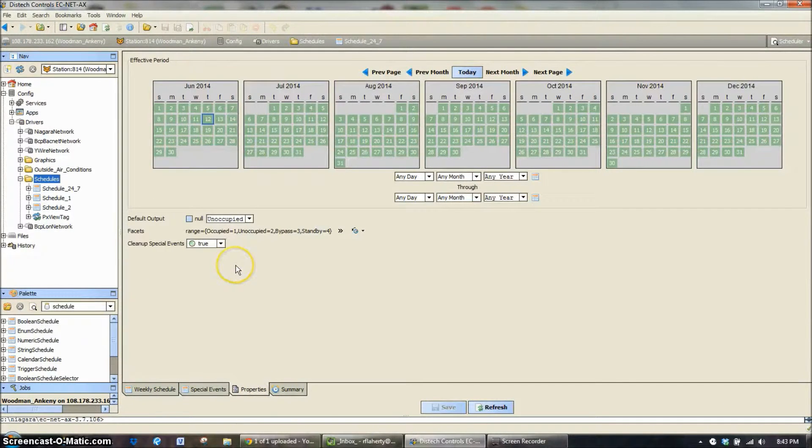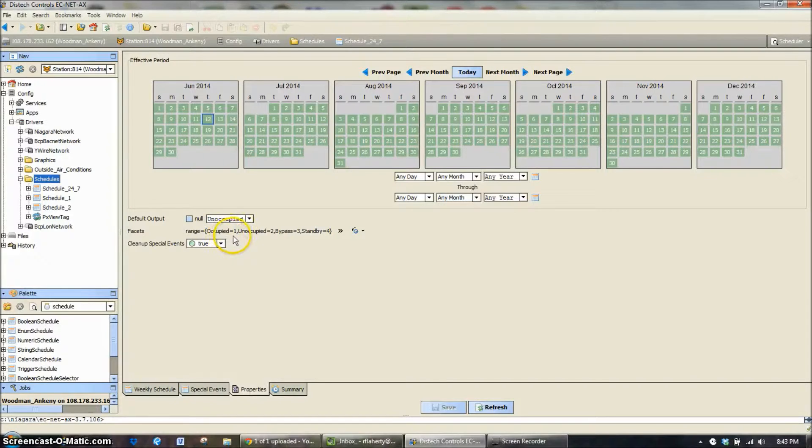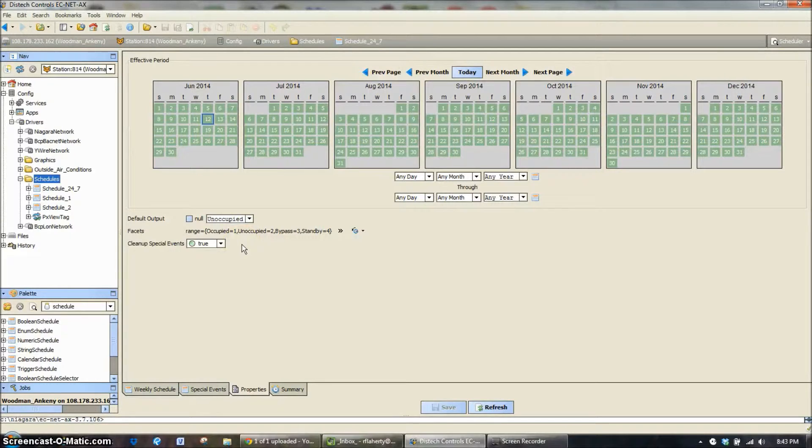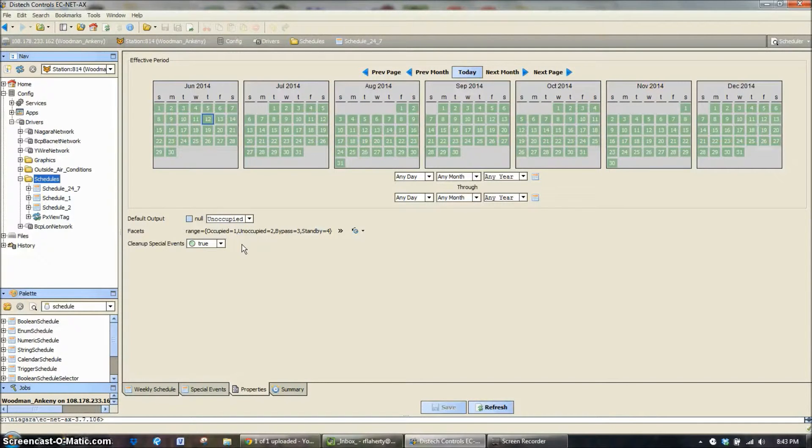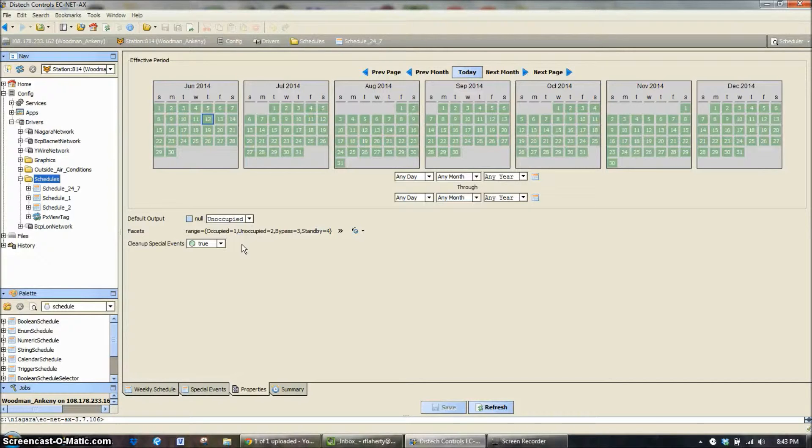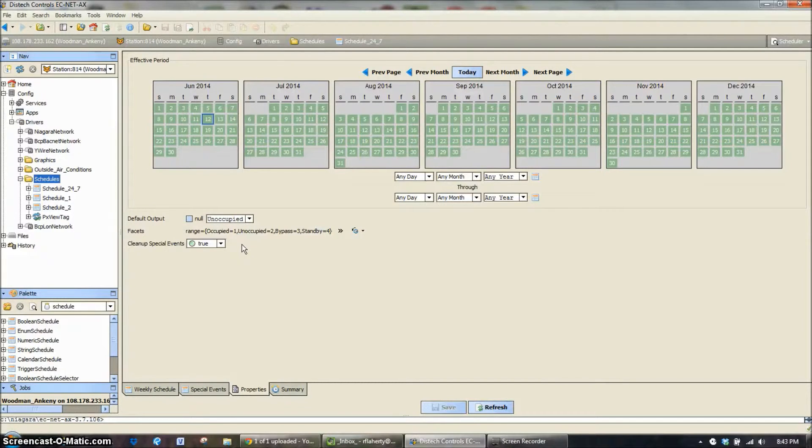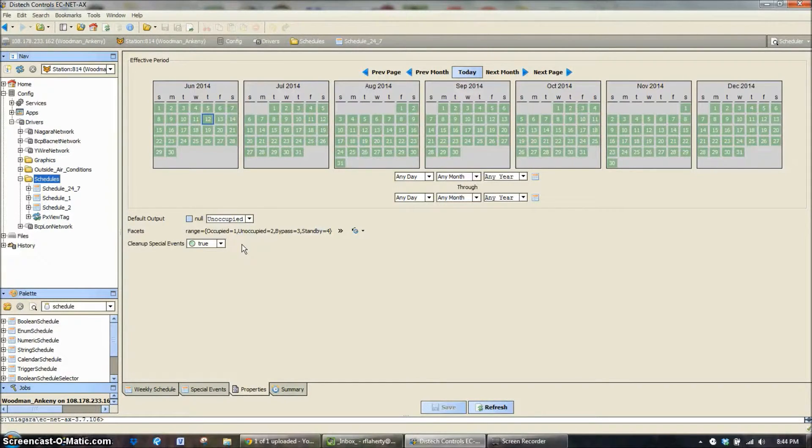In this case, an enumerated schedule has facets set up for occupied equals the number 1. Let me explain - an enumeration is simply a number, maybe 1-100 or 1-4 in this case, that has a text value or some sort of information associated with each number. So the program doesn't read occupied. What the program reads is number 1, number 2, number 3, number 4.